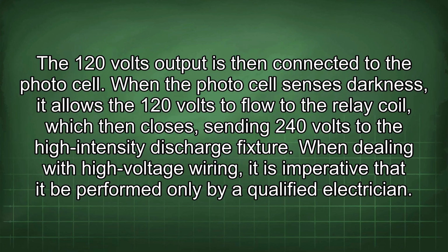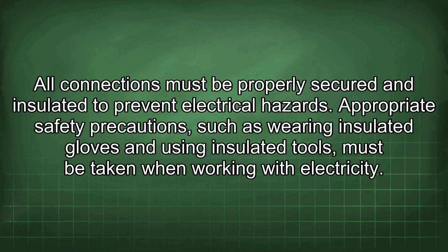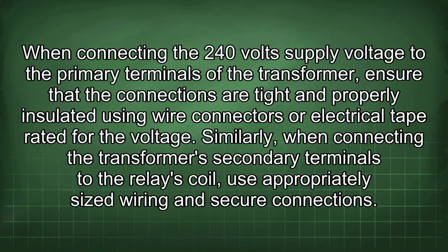When dealing with high-voltage wiring, it is imperative that it be performed only by a qualified electrician. All connections must be properly secured and insulated to prevent electrical hazards. Appropriate safety precautions, such as wearing insulated gloves and using insulated tools, must be taken when working with electricity. When connecting the 240 volt supply voltage to the primary terminals of the transformer, ensure that the connections are tight and properly insulated using wire connectors or electrical tape rated for the voltage.